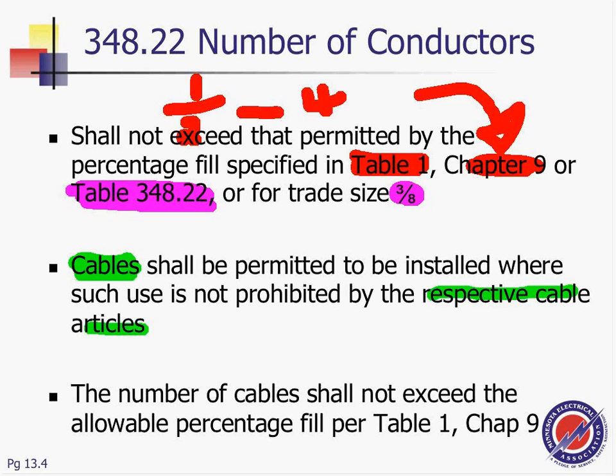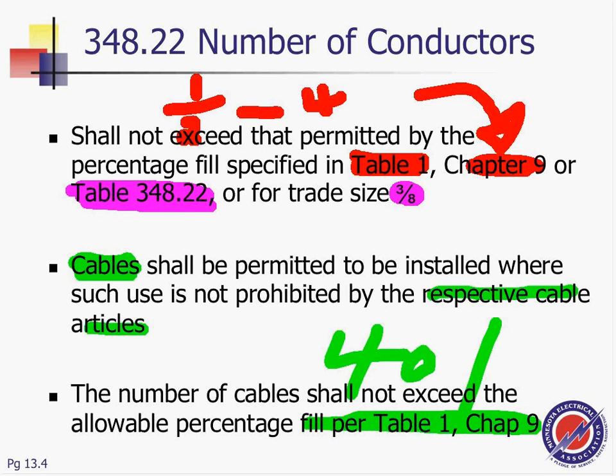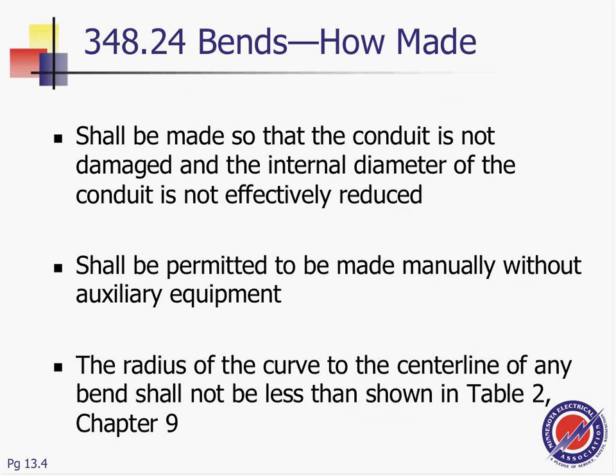So no cable shall exceed the allowable percentage fill. You can't fill more than 40%. You guys remember, for all conduits, the magic number for more than 2 conductors is 40%. This conduit is like any other conduit or surface mounted raceway. It's 40% fill. You cannot fill more than 40% of that baby. Any questions about the fill? I can't emphasize the 3/8 enough. So please remember that 3/8, and I'll flip a few pages and we can go to that table in a second.